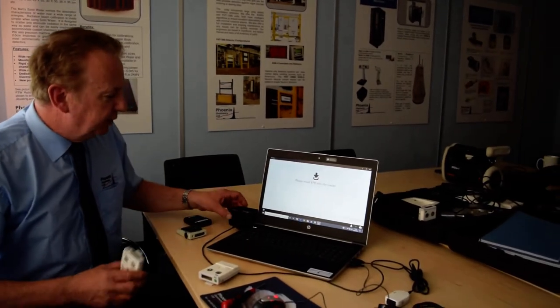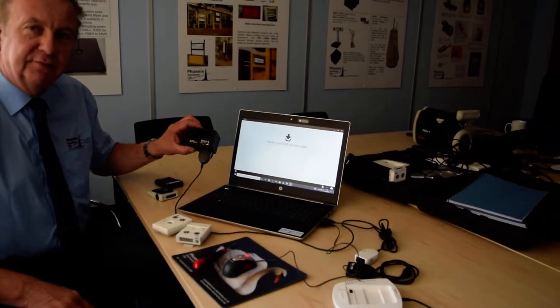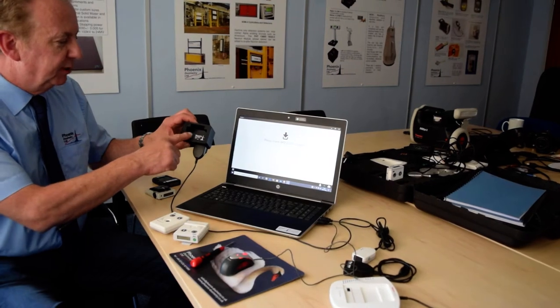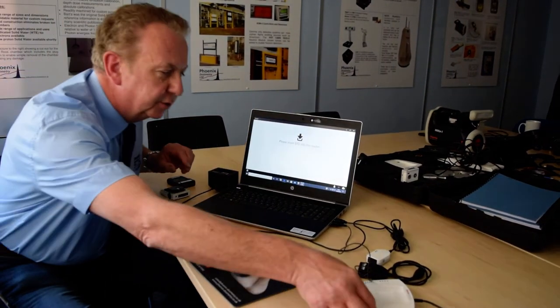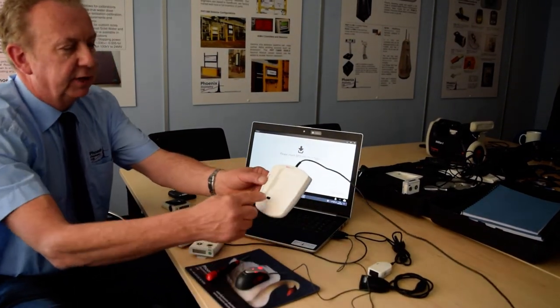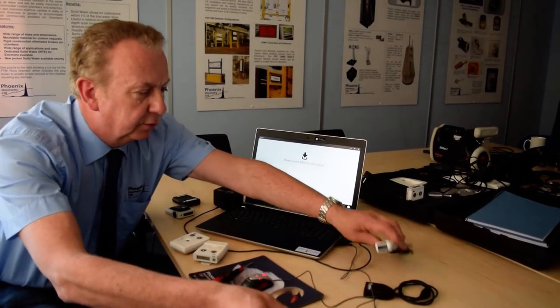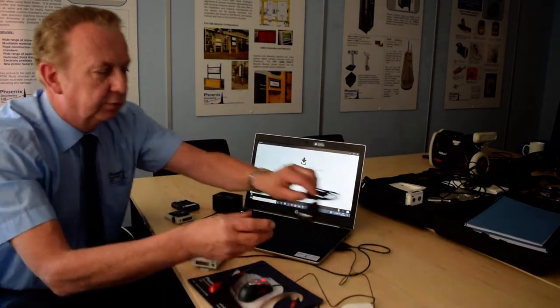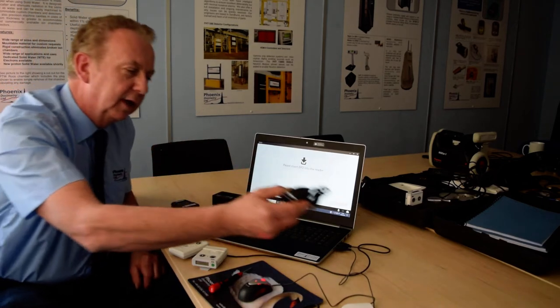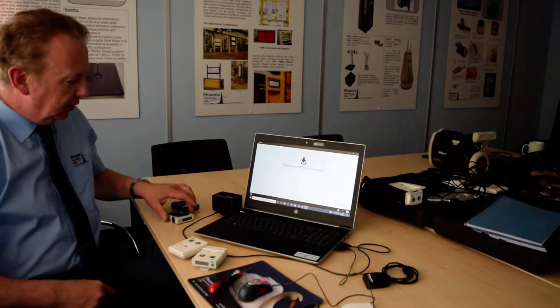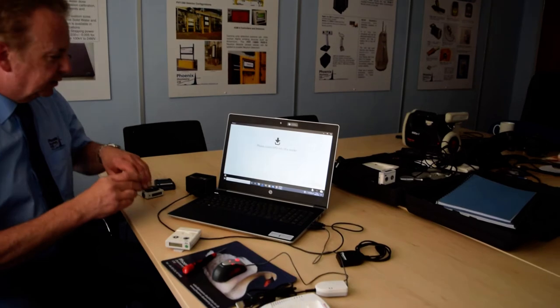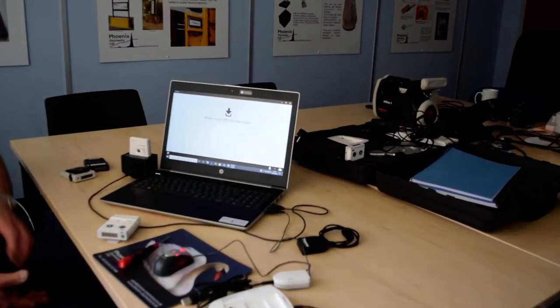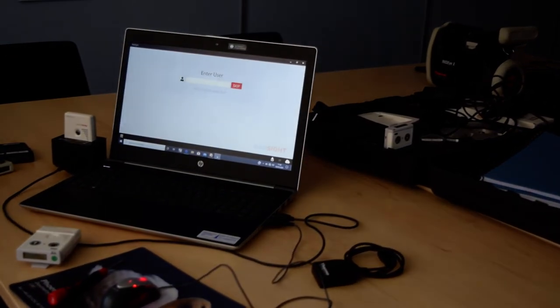Now, there are several sorts of docking stations available for the RadSight software. There's our own EP dock here from Phoenix, but you can also use the standard platter one from Thermo Fisher, or a simple dongle from Thermo Fisher, or the older 2.5 IR station as well. So if I now drop my dosimeter into the issue station, it reads the dosimeter.